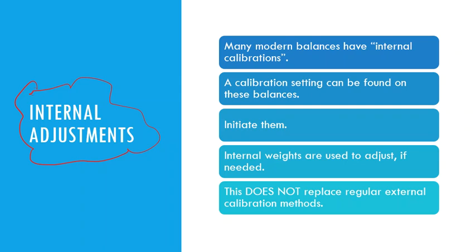So we call these internal calibrations. This doesn't really require a calibration weight set. There's actually something already built into the system, built into the balance. It does this on its own, and it's almost like a backup or a double check because they know that some people have no clue that you're supposed to calibrate your balances all the time. I mean, I've been in laboratories for years, and they've had no clue that this is what you were supposed to do. They've had those balances for 15 years and still think they're working fine, and they probably aren't, or they're not really calibrated like they're supposed to.